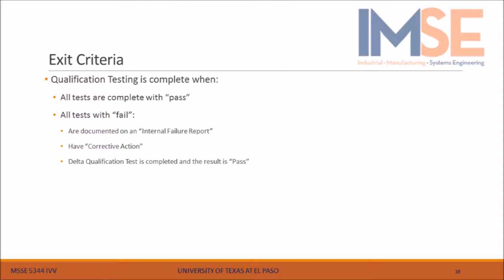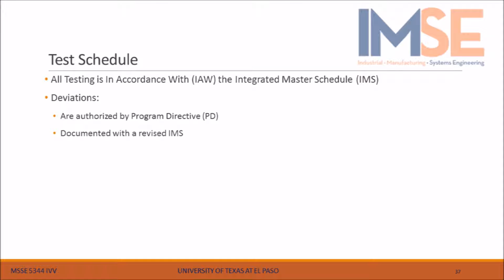Qualification testing can be considered to be complete when all tests are complete with pass, or when all tests with fail are documented on an internal failure report, and have corrective action, and a Delta qualification test has been completed and the result is pass. All testing is in accordance with the integrated master schedule. This ensures that all stakeholders are present and have notification well in advance. Any deviations from the IMS must receive prior authorization by a program directive and will be documented with a revised IMS.